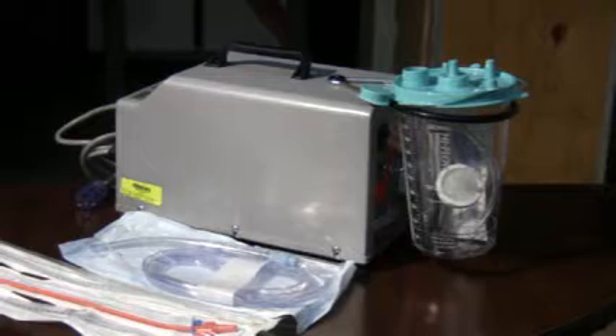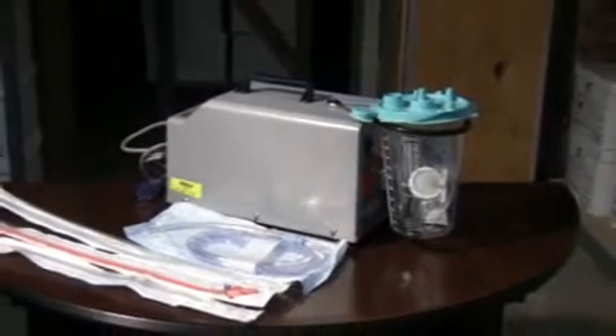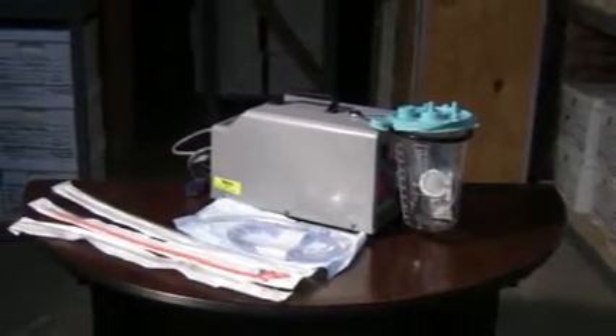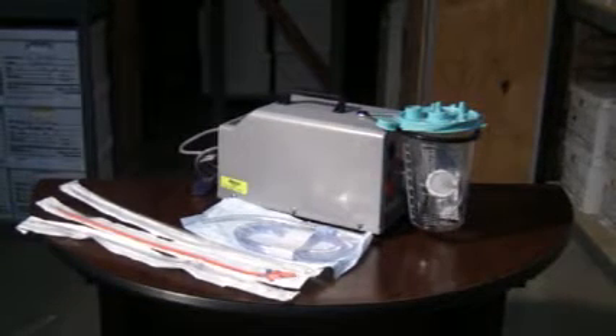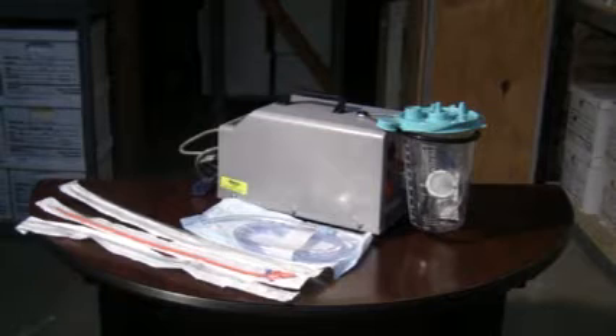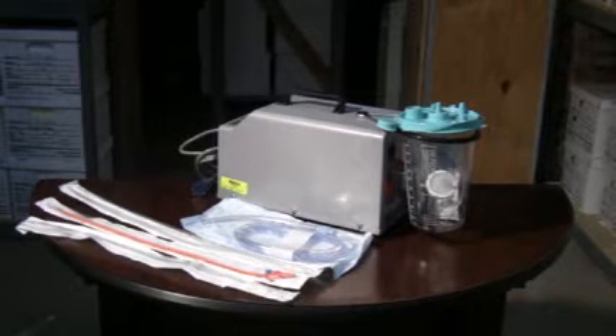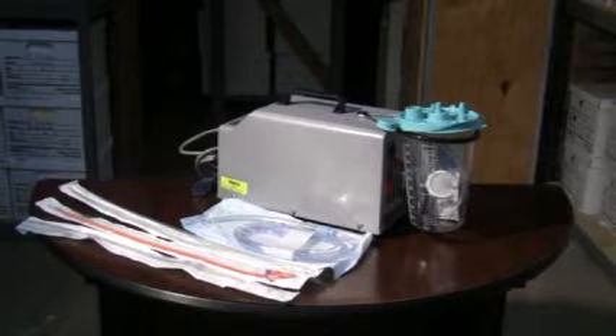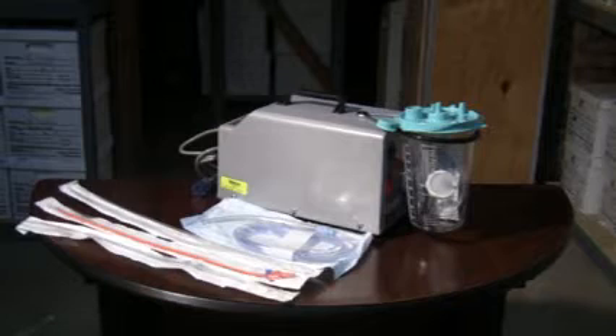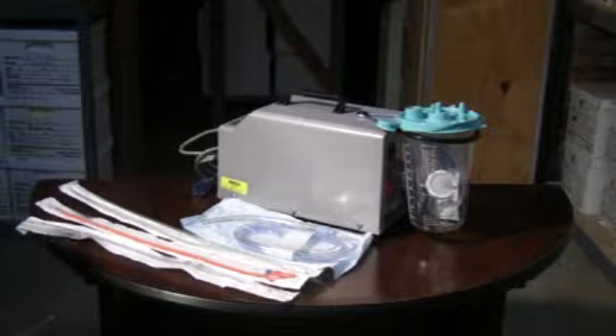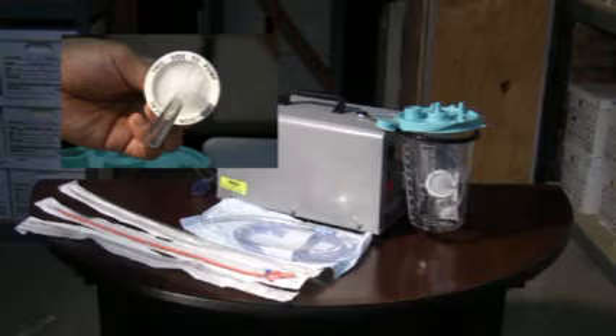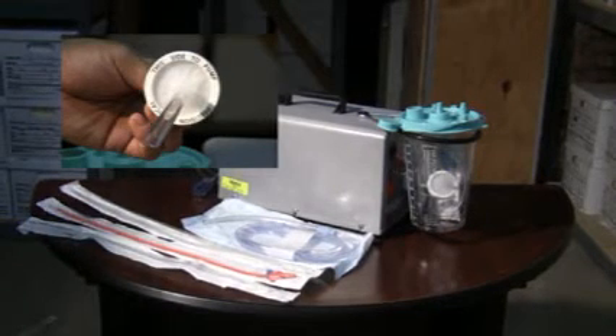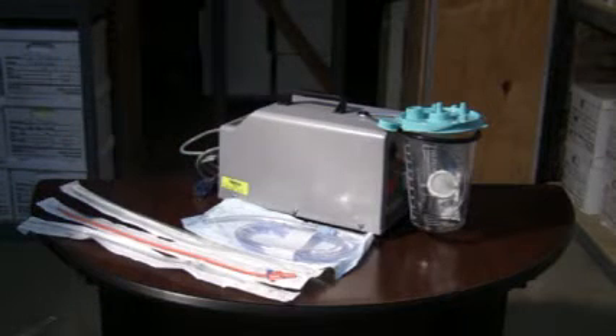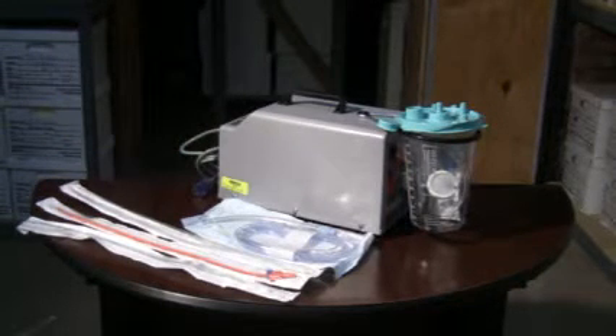The dimensions of your actual intermittent suction machine are 15.88 inches long by 7.38 inches wide with a height of 10.13 inches. And it does weigh approximately 21 pounds. In order to get maximum operating range, it should be at a normal operating room temperature anywhere between 50 degrees Fahrenheit to 104 degrees Fahrenheit. You also do have an inline hydrophobic filter with this suction machine as well, which does help and act as an overflow stop protection filter to prevent the vacuum pump from damage in case of overflow during the time of suction.